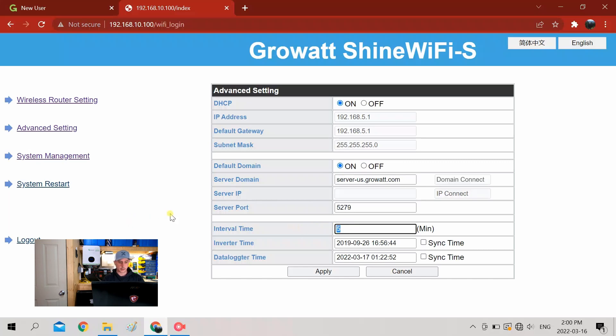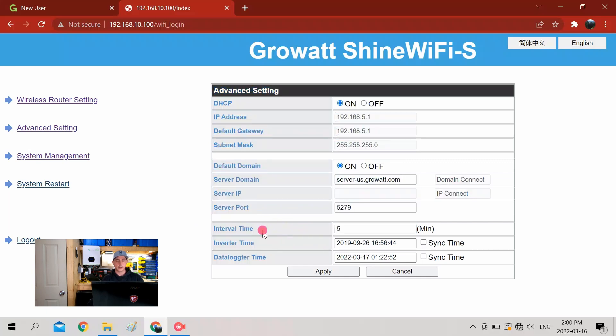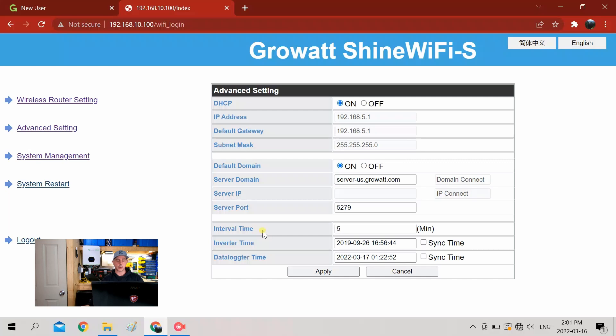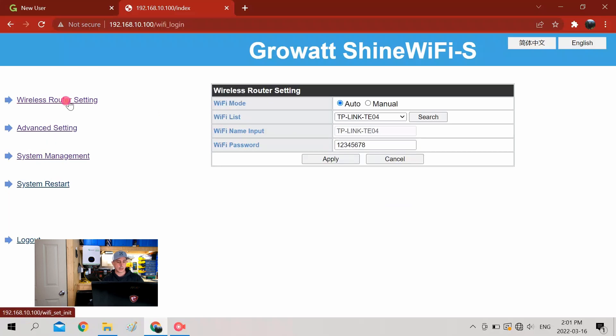Another thing I'm going to change here is the interval time. What this is, is basically it will send the signal out to the server and then you'll be able to retrieve it. So every five minutes by default it'll do that. If you want to increase your accuracy of what you can see of what your unit's doing, you can decrease this time so you'll have more of a picture of what's going on. So we're going to apply those settings.